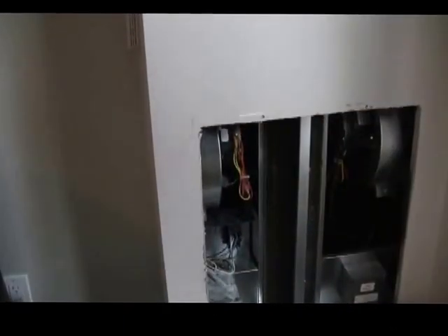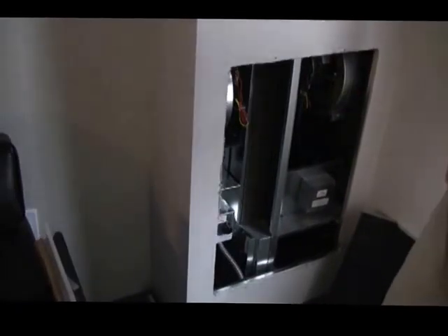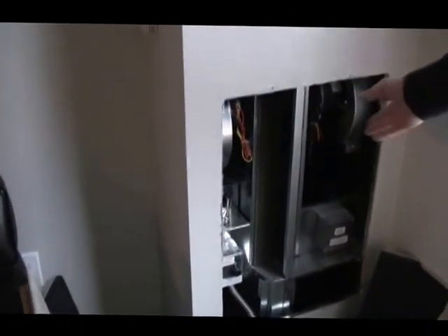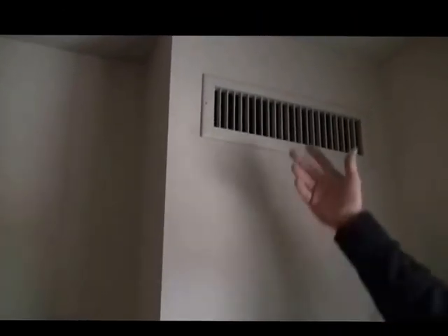Behind that cabinet there are 2 removable panels that cover the blowers, so you can access the blowers there. There's a power disconnect. These units have a central power source. They're powered by the generator. You cannot turn the power off from the panel in the apartment. This is the only disconnecting means for the power for the unit here. To go further back, you have to go to the mechanical room on each floor in order to turn the power off to multiple units. They're a simple unit: blower, a couple of relays, coil. In the top compartment there's a snap disc that tells it whether it's heating or cooling. That's basically it.